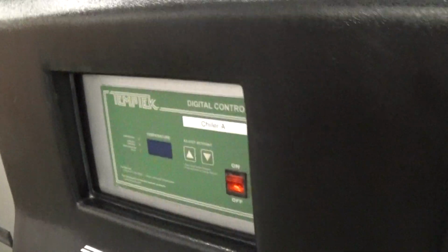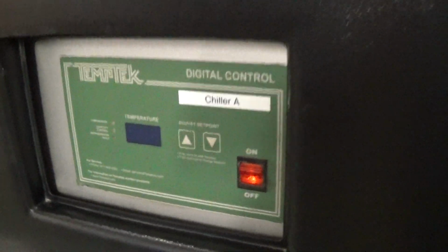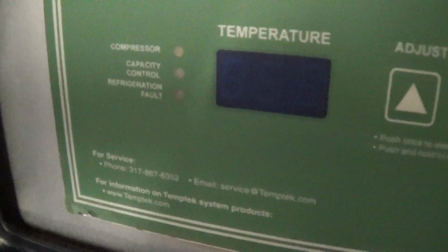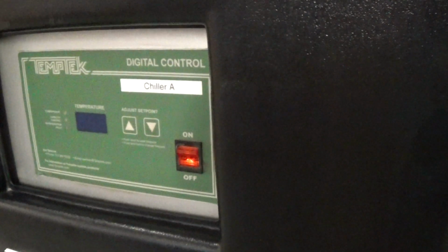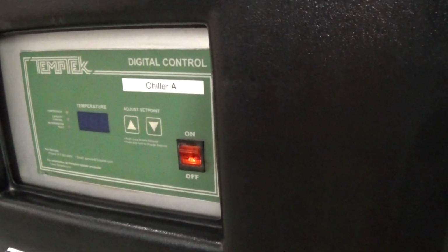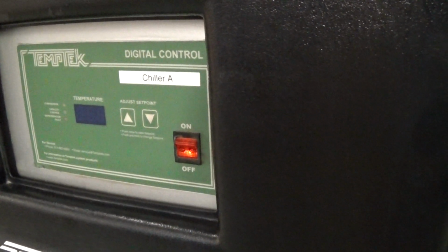Before we turn it on, because it is kind of loud, especially in the shop here, the unit operates on a differential and has hot gas capacity control. So we're going to set it down to 48, and then the chiller is going to chill down to 48 and a degree or 2 below that.